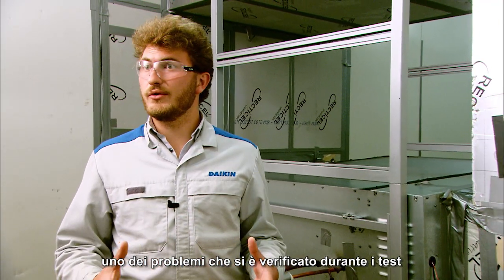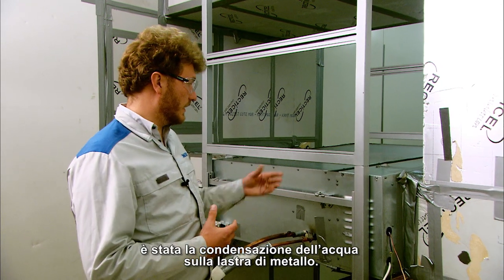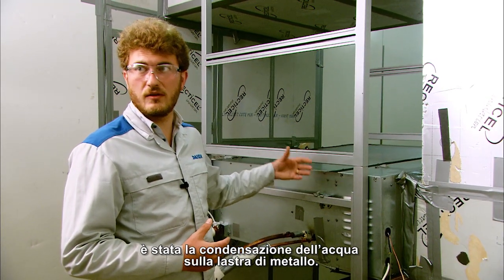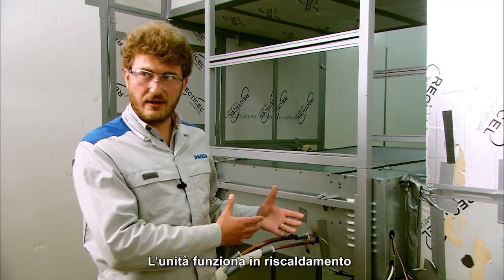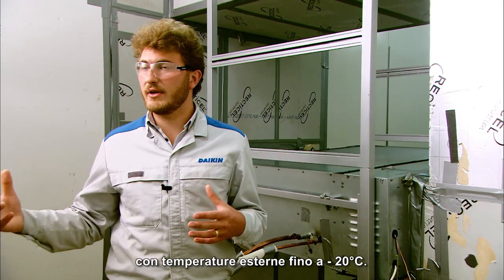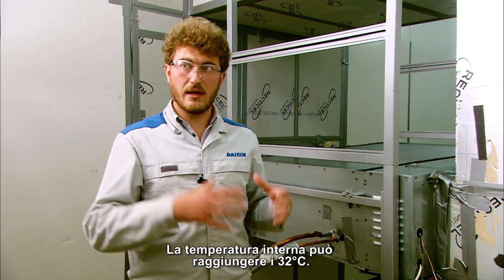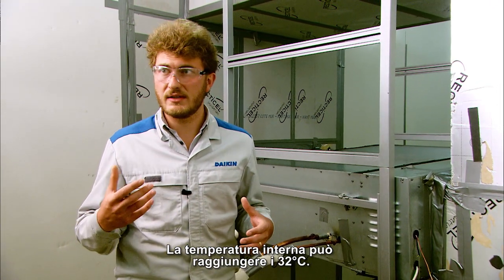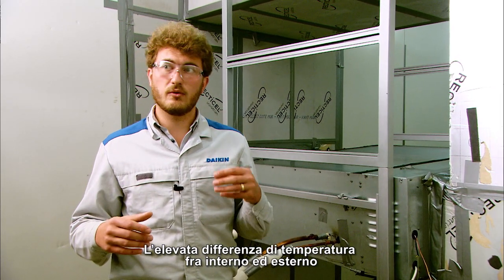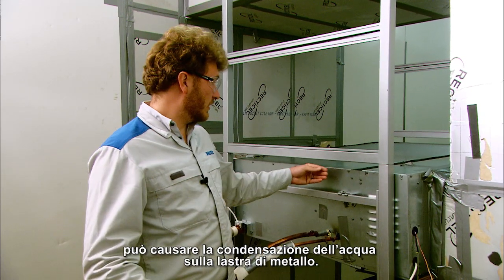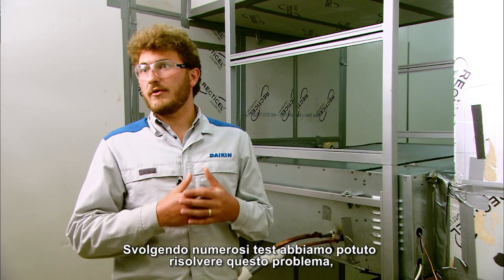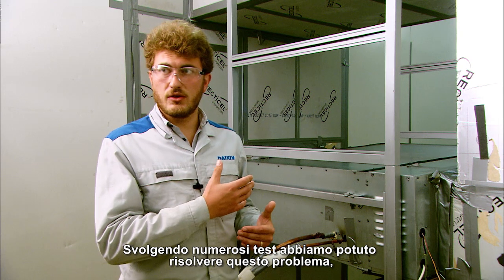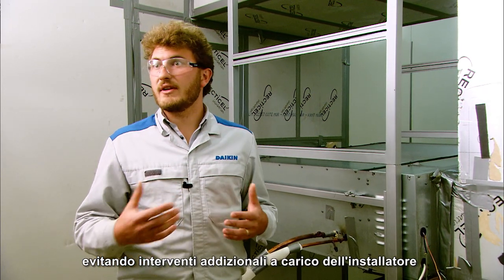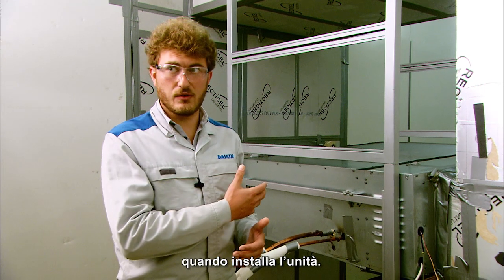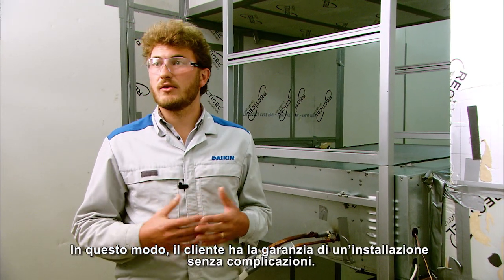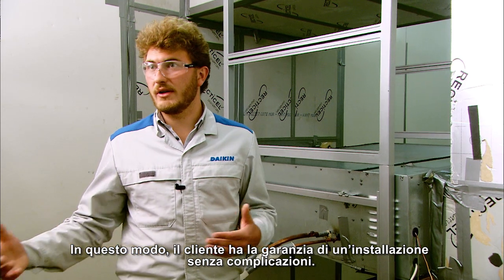One of the problems which occurred during testing was the condensation of water on the sheet metal of the unit. If the unit is in heating operation, the outdoor temperature can be as low as -20 degrees. Indoor temperatures can reach 32 degrees. This huge temperature difference between indoor and outdoor air can cause water to condense on the sheet metal. By performing a lot of tests, we could solve this issue, and the installer doesn't have to take any additional countermeasures when installing this unit. This way, the customer can also be guaranteed trouble-free operation.